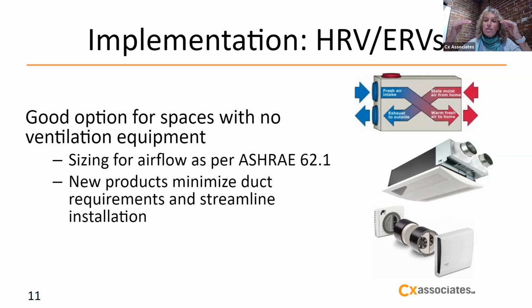What the recovery unit will do is, inside the unit, have enough surface area where the two will transfer their heat. Now your exhausted air started at 74 and is maybe coming out at 50 degrees. The fresh air is taking that heat, and if it started at 10 or 15 degrees, it's now coming out at, say, 50 or 55 degrees. That's a very efficient way of bringing in fresh air, much better than just having a direct fresh air intake. And it's also much more comfortable.